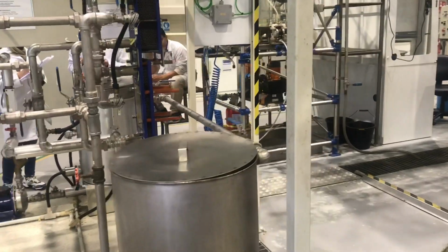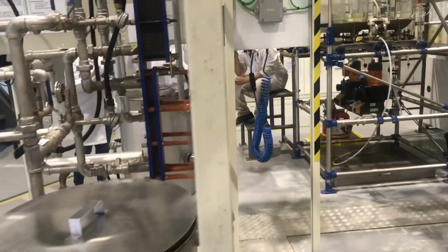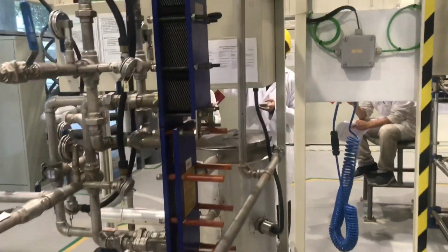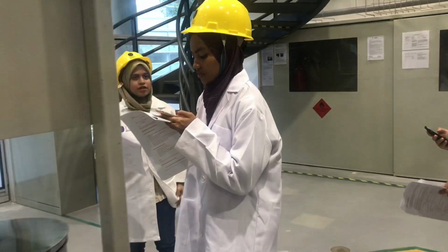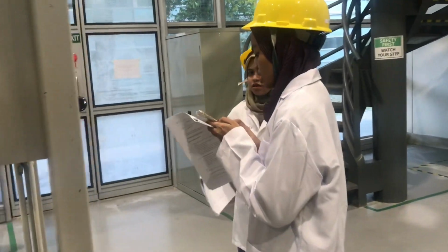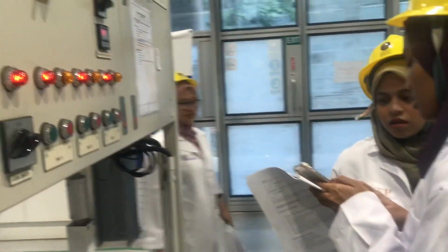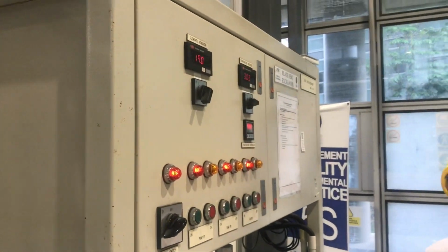The pumps are protected from dry run by an electronic level switch installed inside each of the sump tanks. A low level in the cold water tank will automatically cut the electrical supply to the pump, and a low level in the hot water tank will electrically cut the supply to the heater and to the pump.